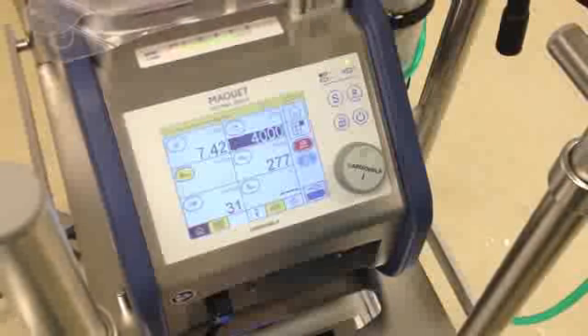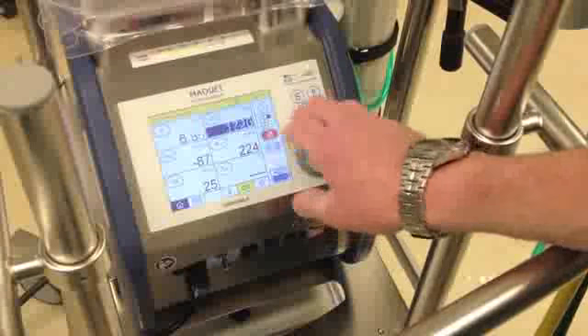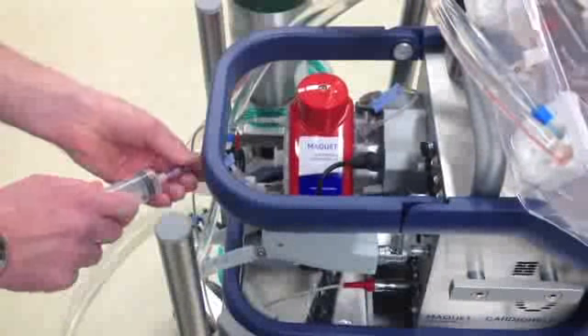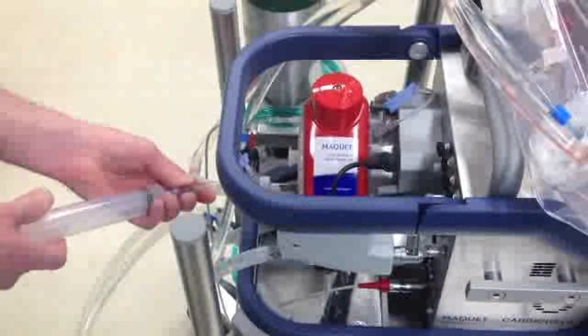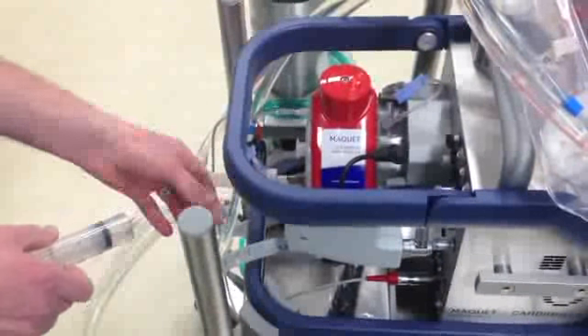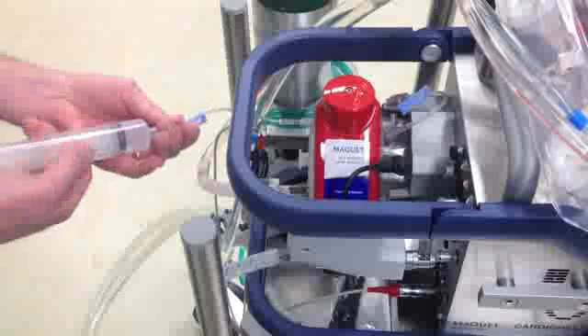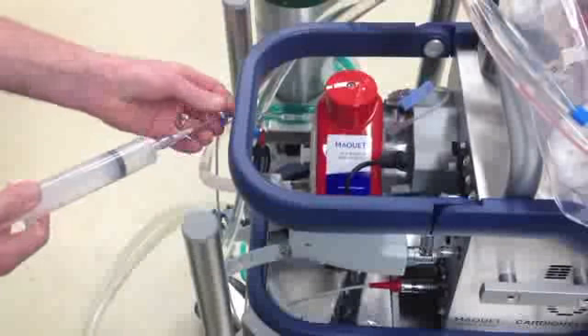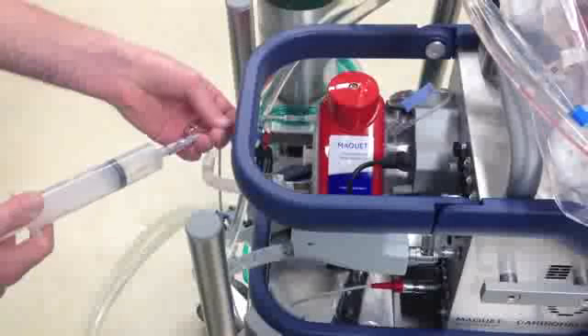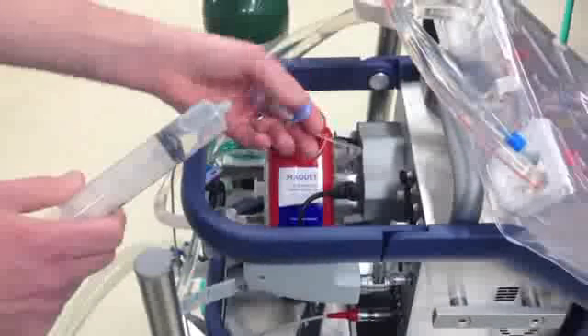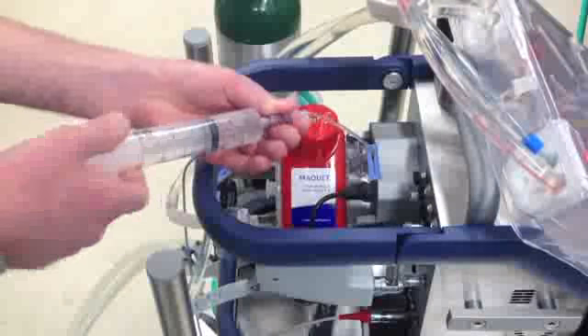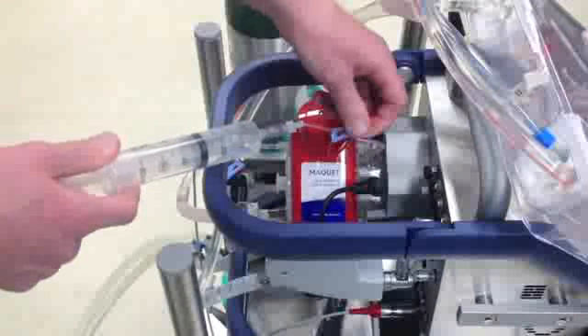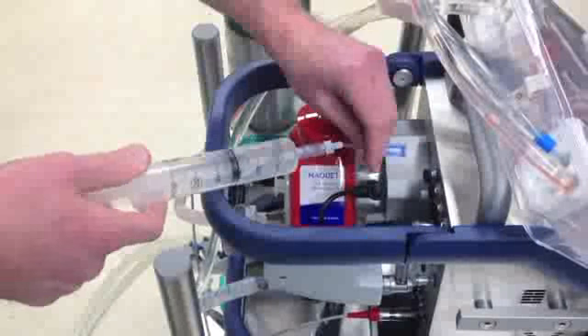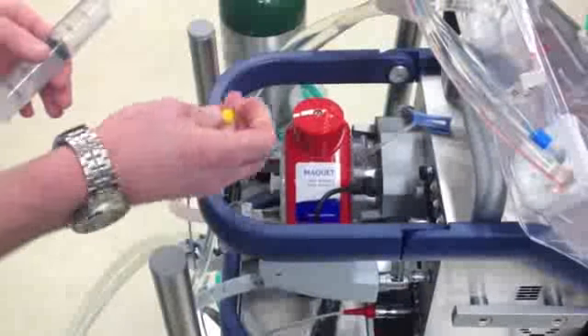And then once that's done, and you don't detect air, you'll turn your RPMs back down to 0, essentially stopping flow. You'll go back to the rear of the machine, and you'll use a syringe to de-air the extension tubes that we placed on the caps. If it was Maquet, they would be calling this step where you burp the caps, but since we removed the caps and put extension tubings, you have to use a syringe, and then you clamp off the extension tubings, and that's how we prevent air from entering the system. Then you'll take that yellow cap that magically disappeared earlier, and you'll place it on the de-airing port.